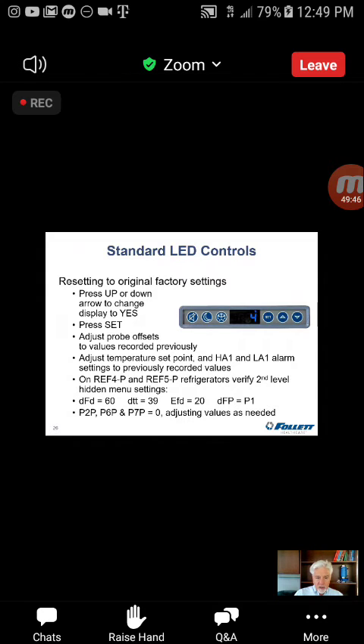So you want to make these changes. So if you go into each one of these settings and you see a value other than the one being displayed, then you want to make that adjustment. Now remember, defrost termination time limit, defrost termination temperature, okay? Fan delay. When the unit's shut down, we run the evaporator fan for an additional 20 seconds, and our defrost termination probe is going to be probe number 1. The original ones were probe number 2. And so, like I said, these enhance the unit's performance.